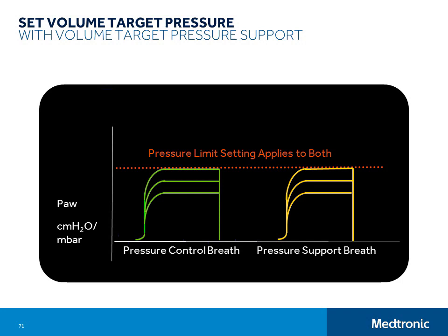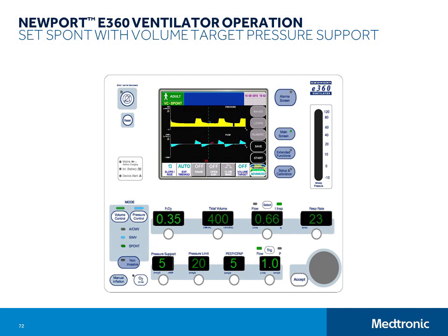Then push either the volume control or pressure control breath type button until SPONT lights up. It doesn't matter whether you choose volume control or pressure control SPONT mode, the end result will be the same. As with all other modes and breath types, make sure to set all parameters on the control panel and GUI that are not dimmed or grayed out, and also check the alarm settings.